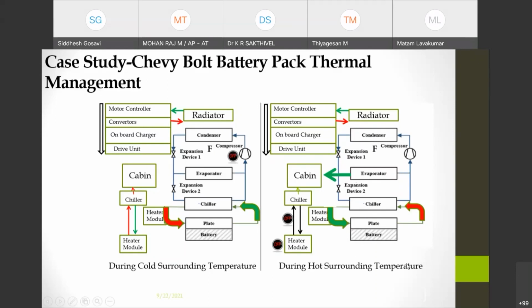Now, there are too many paths in this circuit. When I say control strategy, I mean these operating parameters. At what temperature should I allow it to cool? I can't pass the water ethylene glycol mixture at, say, minus 5 degrees Celsius; I have to pass it at 5 degrees Celsius. All those limiters need to be set in the BTMS unit, the thermal controller. I have to monitor the flow rate of the pump. If the battery pack is not getting cooled in spite of doing all of those things, then we have to check where to increase the flow rate. We have to increase the compressor RPM if my chiller system is not getting cooled. If we move backward, there are 4 or 5 parameters that we need to identify. If a certain objective is not getting fulfilled, we have to tune those parameters and re-experiment again until the result is obtained.